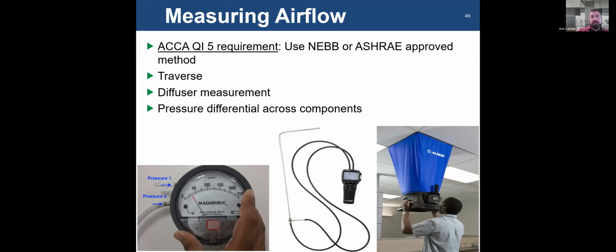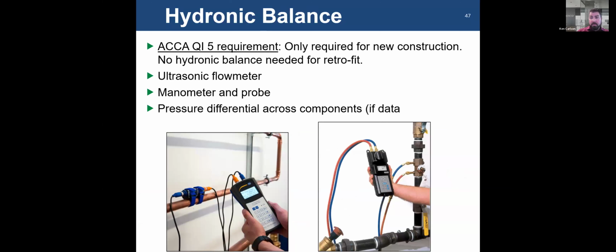To measure your airflow, that can be done on branches, and that can be done at the main trunk, or you could take a pressure differential across components. Manufacturers will often post pressure differentials for given airflows, across coils or units. You can use that and correlate it to the chart, figure out what your differential pressure is across the equipment, and then correlate that to an airflow. It'll get you close. Best method is a traverse if you're trying to find airflow, or a direct measurement via hood. Same thing goes for water.